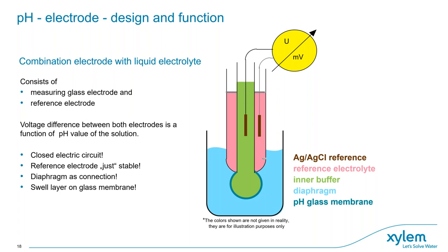Therefore we use the reference electrode as a counterpart — it should be stable and constant, so we measure only the changing potential at the glass electrode. To measure the glass electrode potential versus the reference electrode, we need to connect the reference with the sample via the so-called diaphragm. This closes the electric circuit so we can measure millivolts with a pH meter and calculate the pH value. The circuit leads from the meter through the inner buffer, through the glass membrane, through the sample, through the diaphragm, through the reference, and back to the meter. Anything that disturbs this closed circuit will disturb the measurement result.